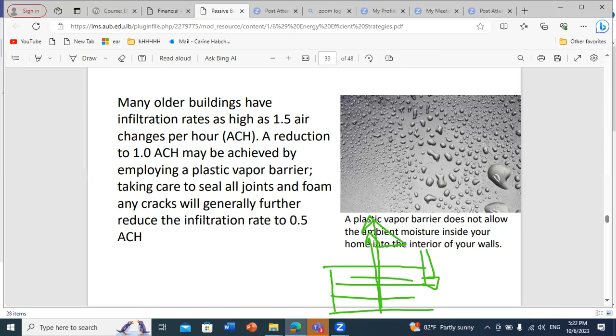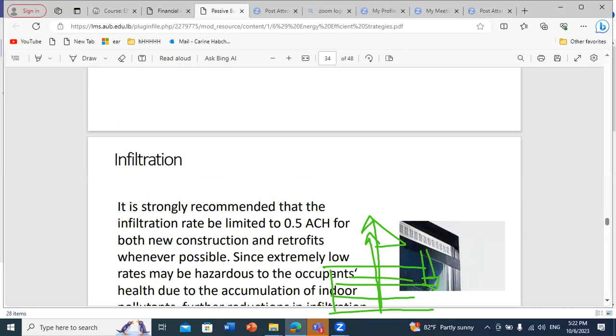So whenever you have your windows, you can put sealing joints to your windows in order to avoid leakages. So you can seal all joints and any cracks that can lead to a reduction to the level of 0.5 air change per hour, which is required. But as we mentioned, you should not go below this level to avoid reduction of fresh air. So you should have good indoor air quality within your space. Now, it is strongly recommended that the infiltration rate should be limited to 0.5 air change per hour for both new construction and retrofits whenever possible.